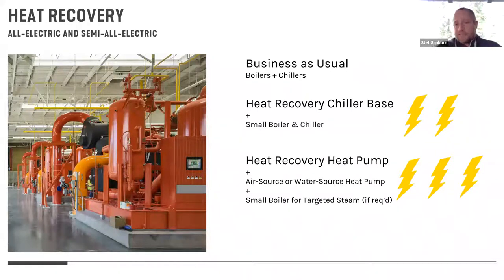For those projects, we're obviously still looking at heat recovery, heat pumps, heat recovery chiller sections, heat recovery heat pumps, and either augmenting that with air source or water source heat pumps to do the peaks and valleys. And that is really dependent on where our really quality source energy is, whether it's outgoing sewage, which I'll talk about in a little bit, or outside air temperatures. We want to find the best source to get the best heat recovery potential.